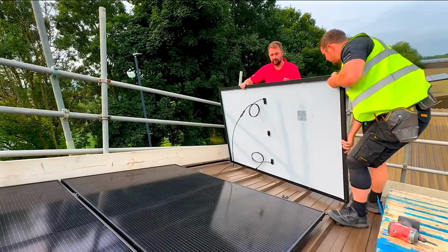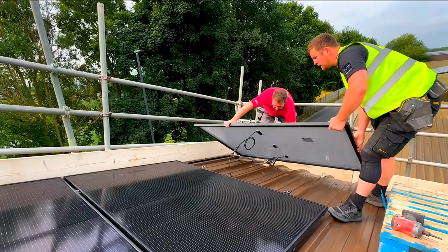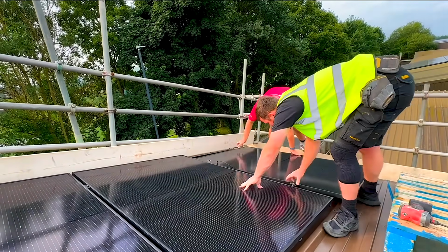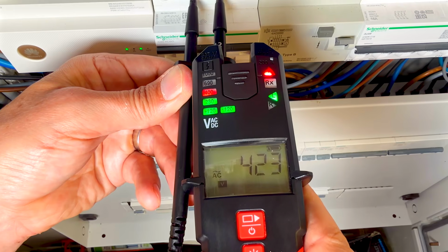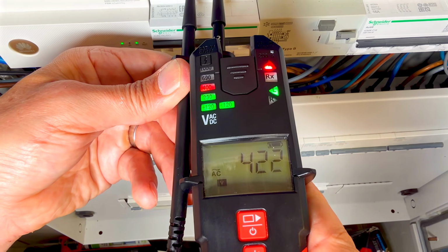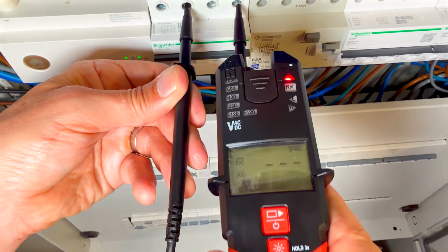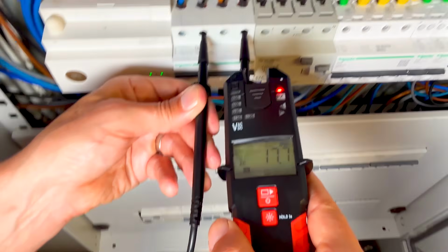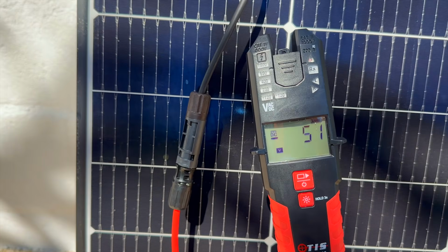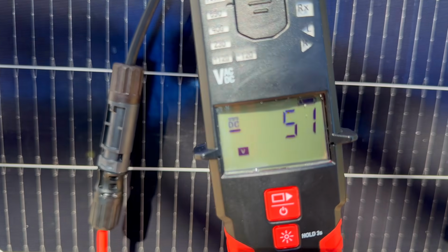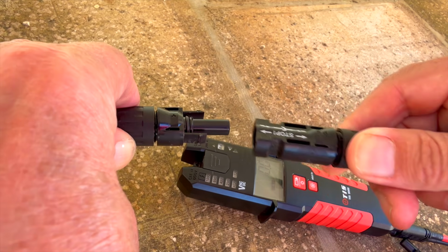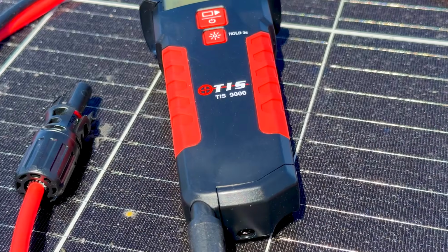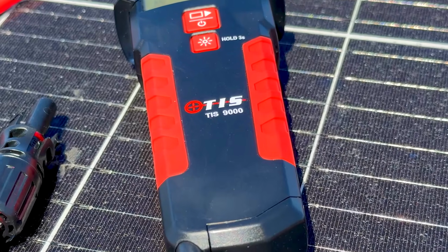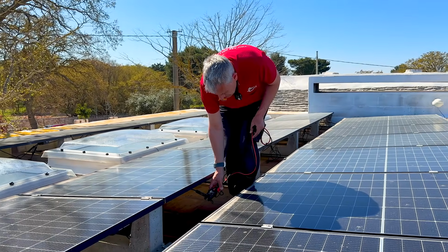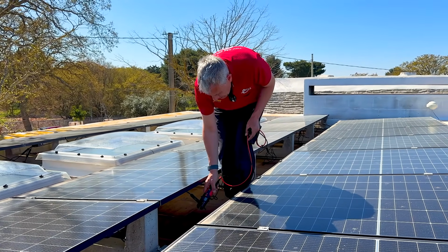If you're working on solar PV or battery storage, this is your reality every day. DC on one side, AC on the other, and no room for guesswork in between. You need to know what's energized, what's isolated, and that your test equipment is telling you the truth. That's exactly where the TIS9000 earns its place. It's not just about proving dead. This is one tool that lets you measure, verify, and fault find across the whole system without constantly swapping kit. Less guesswork, fewer tools, more confidence on site.